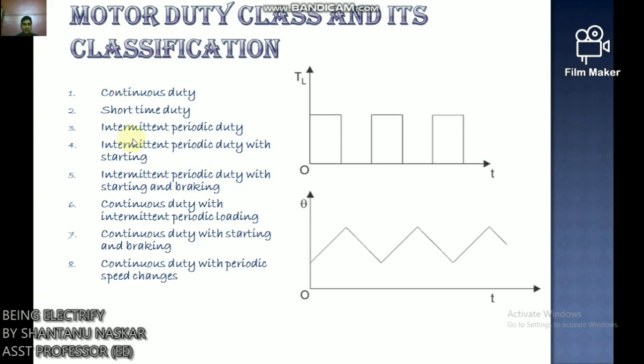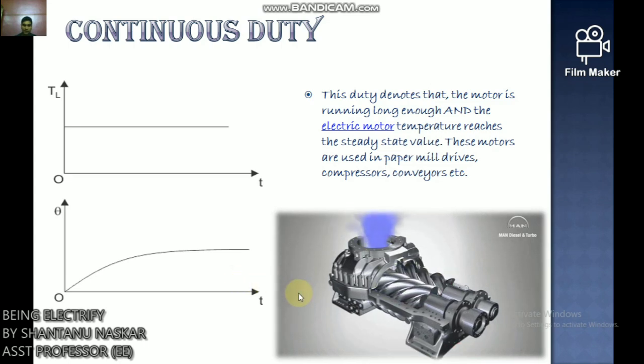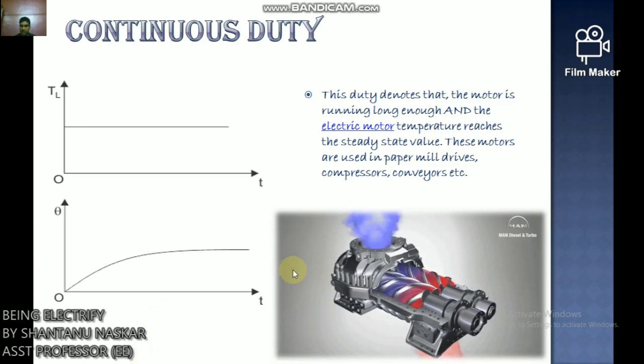The 8 duty classes are: (1) Continuous duty, (2) Short time duty, (3) Intermittent periodic duty, (4) Intermittent periodic duty with starting, (5) Intermittent periodic duty with starting and braking, (6) Continuous duty with intermittent periodic loading, (7) Continuous duty with starting and braking, and (8) Continuous duty with periodic speed change. First: Continuous duty — the motor runs long enough for temperature to reach steady state, used in paper mill drives, compressors, and conveyors.